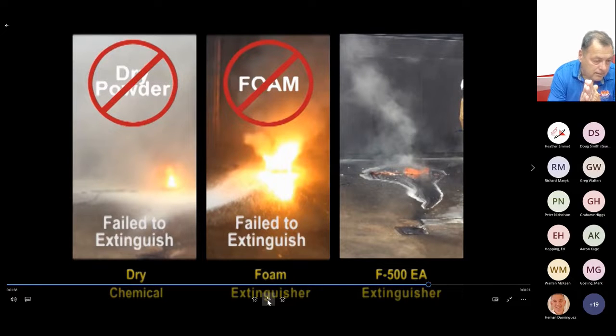And then if you think about what is the #1 Class A fire extinguishing agent in the world, it's plain water. And every test report I look at says we must use copious amounts of water. Well, the reason we're using copious amounts of water is perhaps lithium-ion battery is not a Class A fire.